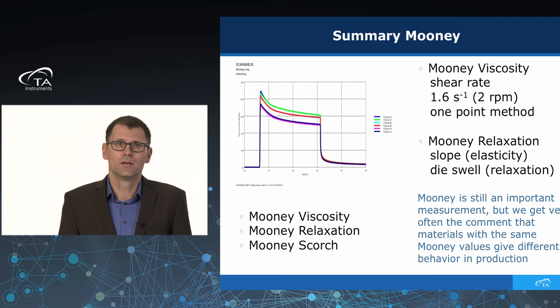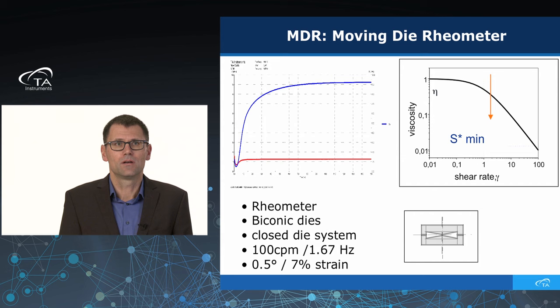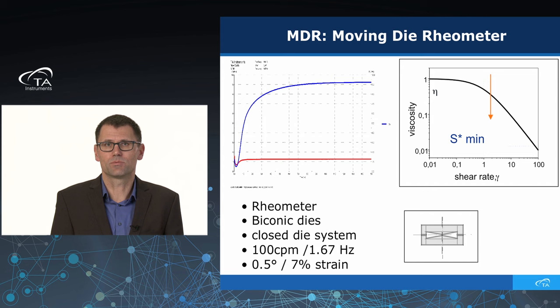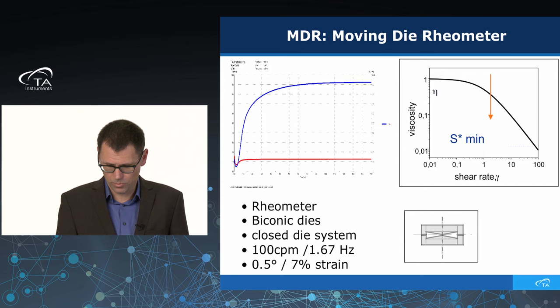The next step is the MDR, the moving die rheometer. The blue curve is a typical cure curve, which we all measure every day in the rubber industry, and the red curve is the viscous part, the S double prime. The rheometers on the market use bi-conic dies — closed dies, sealed with a rubber seal — with a fixed frequency of 100 CPM (1.67 Hz) and a strain of 0.5 degree, which is about 7% strain. But when you calculate the minimum of such a curve, you also have only one point on a viscosity curve — measuring only one shear rate and nothing more.